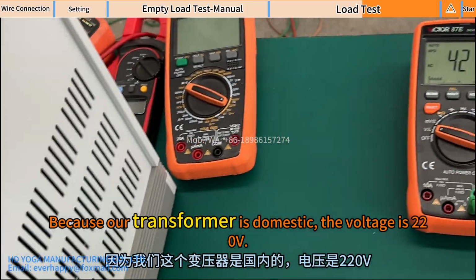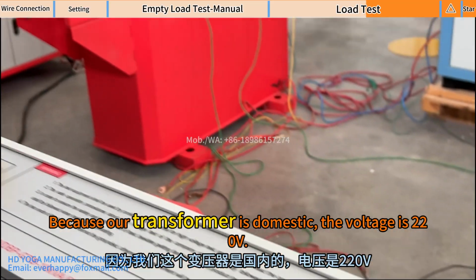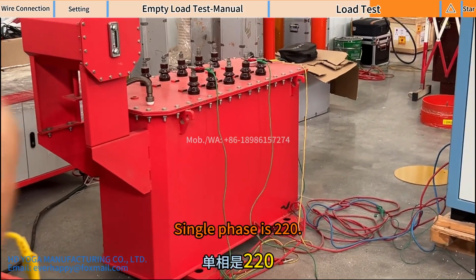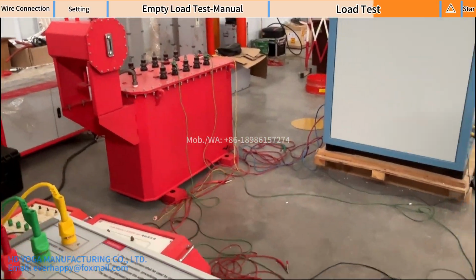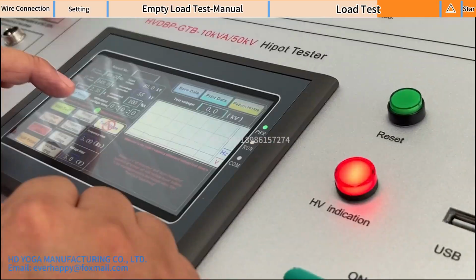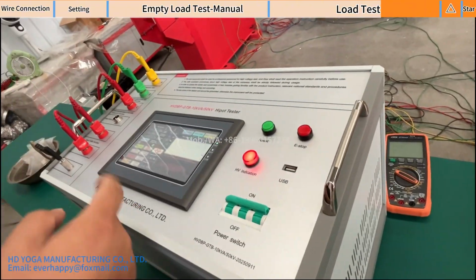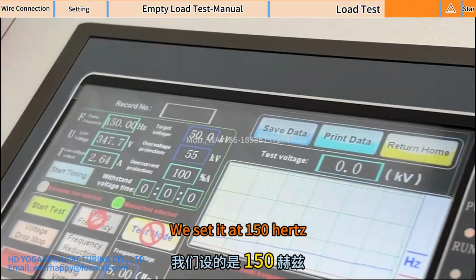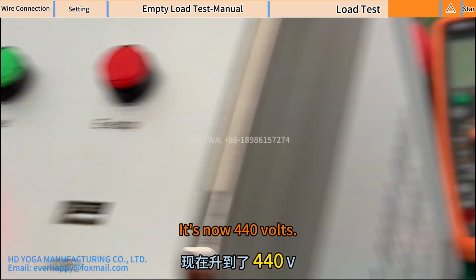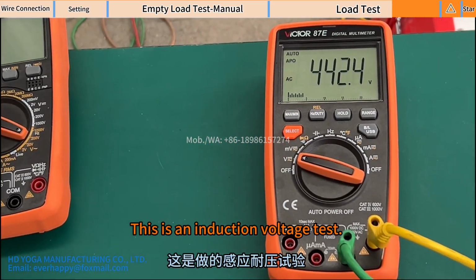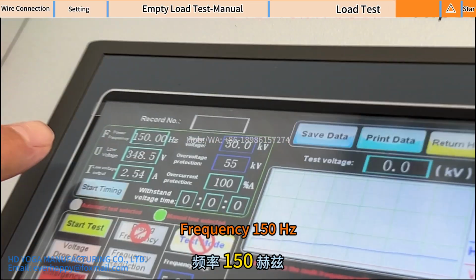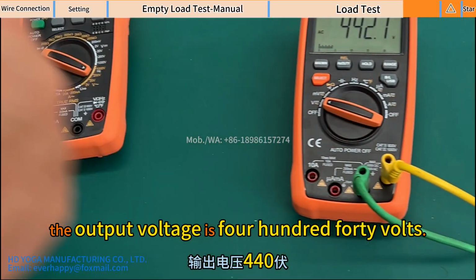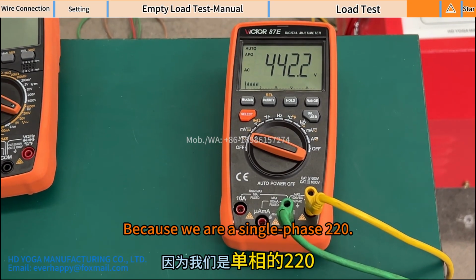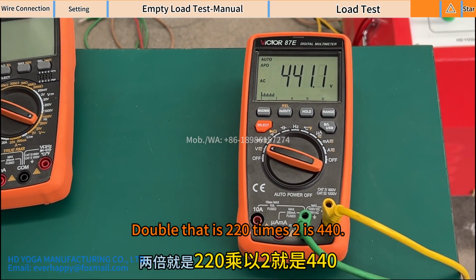Because our transformer is domestic, the voltage is 220 volts. Single phase is 220. Now it's raised to 420. We set it at 150 Hz. It's now 440 volts. This is an induction voltage test. Frequency 150 Hz. The output voltage is 440 volts. Because we are a single phase 220. Double that is 220 times 2 is 440.